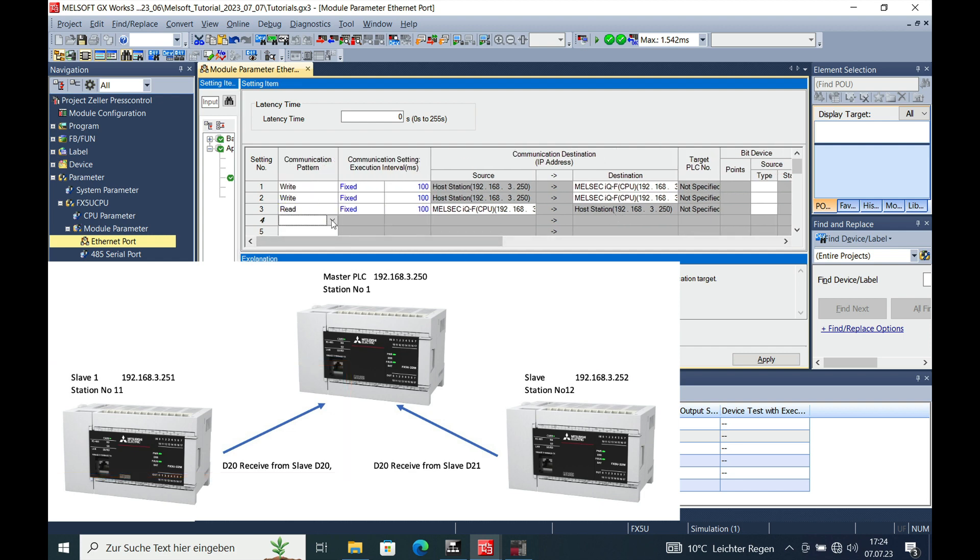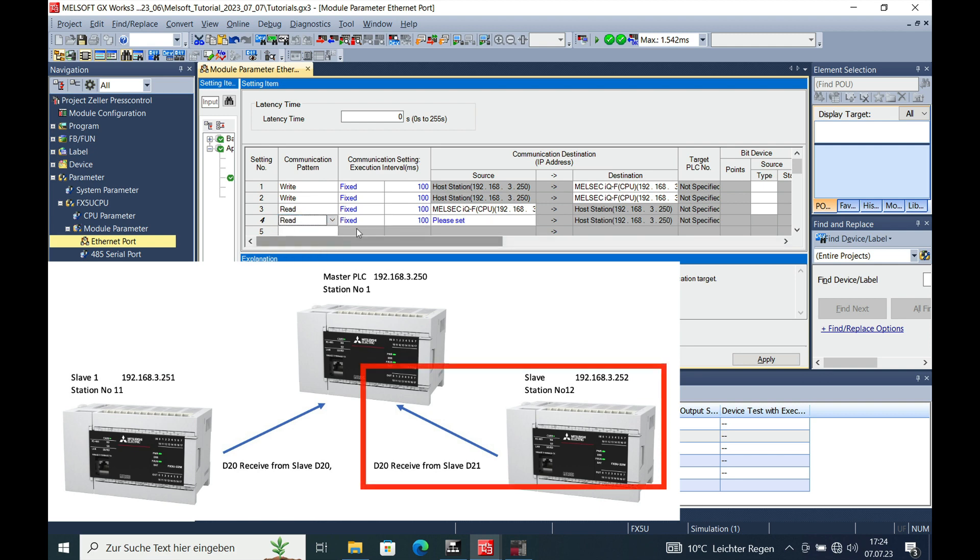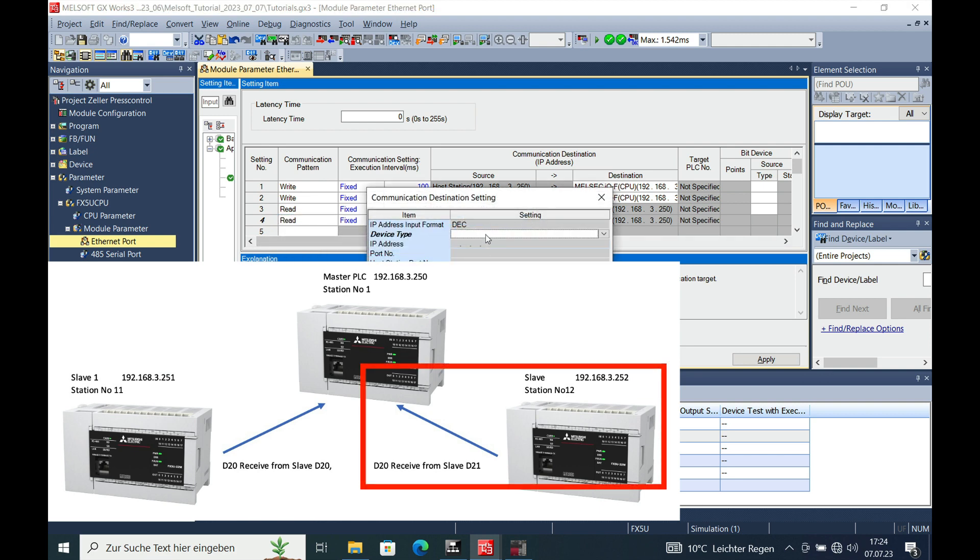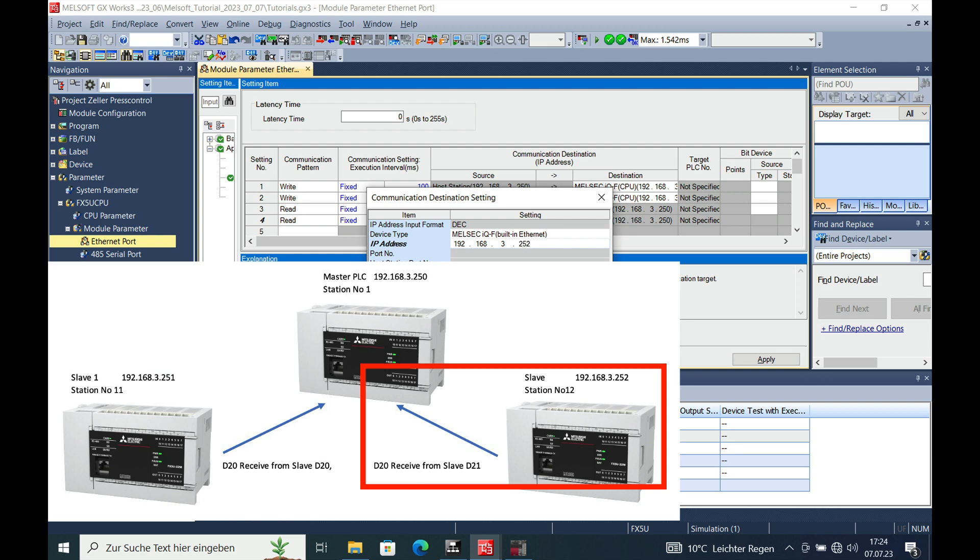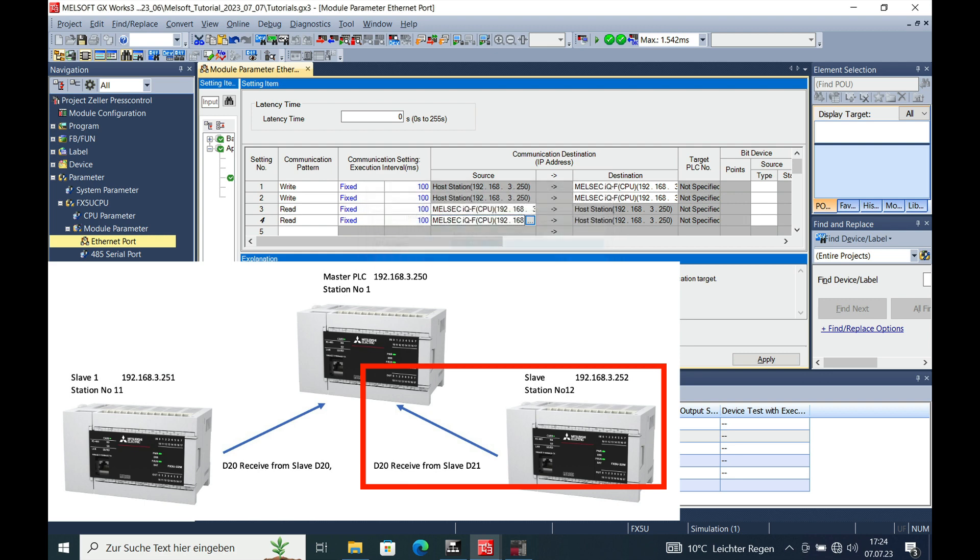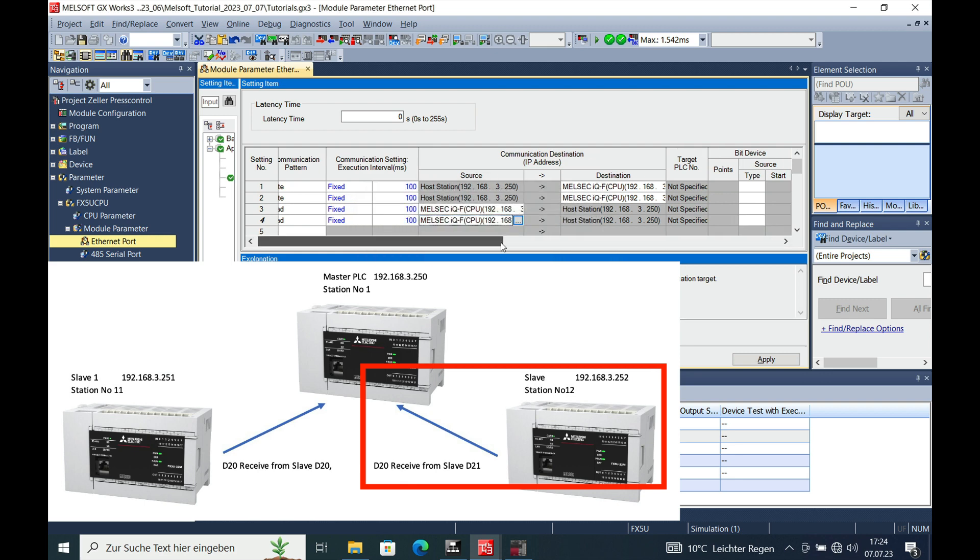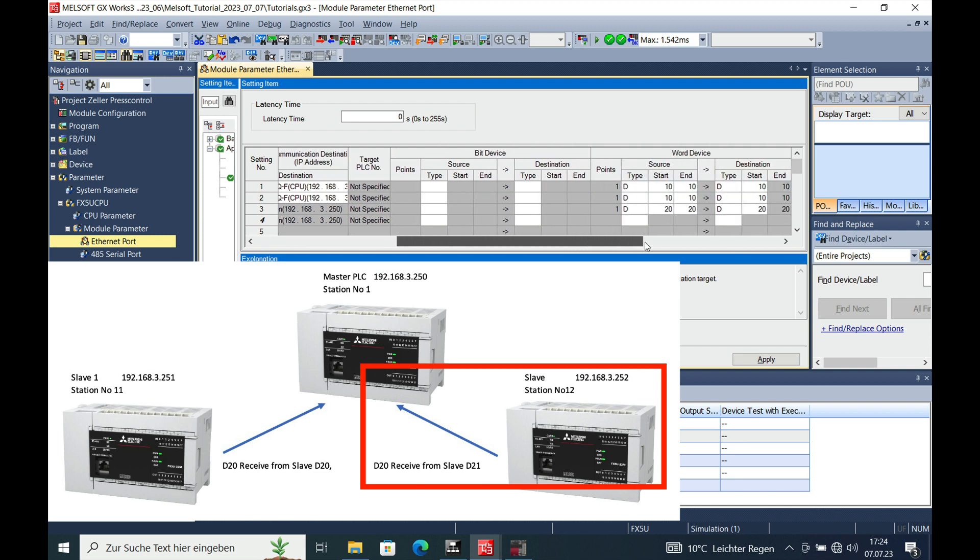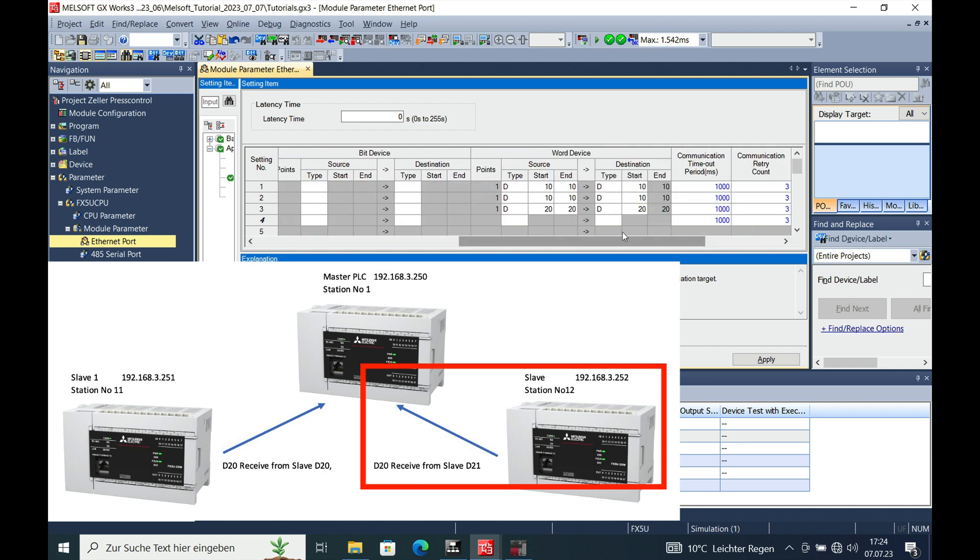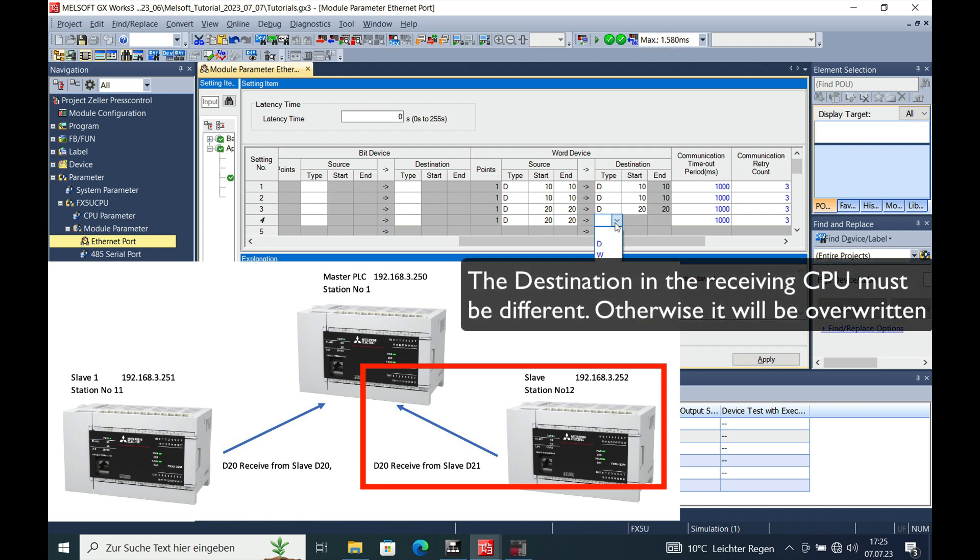And then we do this from the next PLC. We choose 252, 192.168.3.252. And we will be sending or reading the source D20, which is the same register in the source PLC. And we have to write it to a different register, otherwise it will be overwritten and you will have the wrong data. That's why we chose the D21.